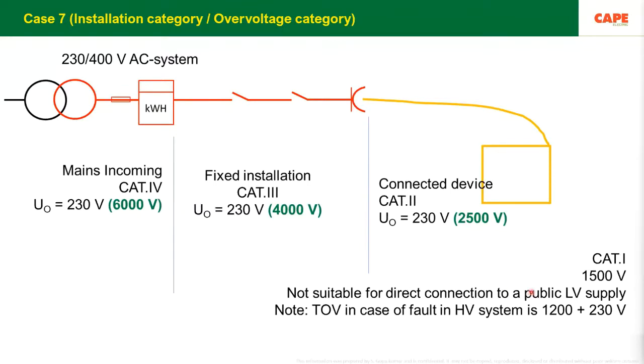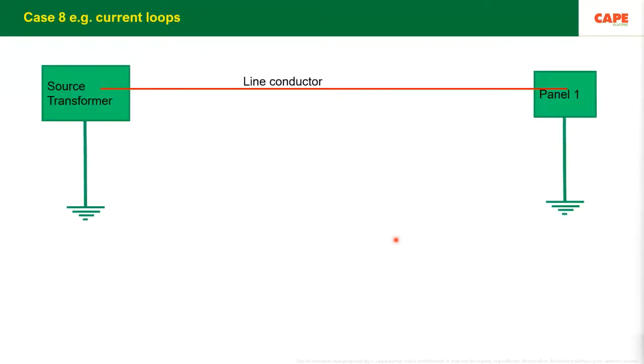What I wanted to tell you is there is a category of device called category 1. Installation category 1 means sensitive electronic apparatus. You should check the manufacturer's catalog, and if the device is of category 1, we are actually not supposed to connect it directly to a power supply coming from the electricity supply company. From the transformer, a category 1 device we are not supposed to connect directly. But unfortunately, in several cases this subject is overruled, nobody bothers. As a result, finally we end up with fire and accident. Case number 8, current loop.